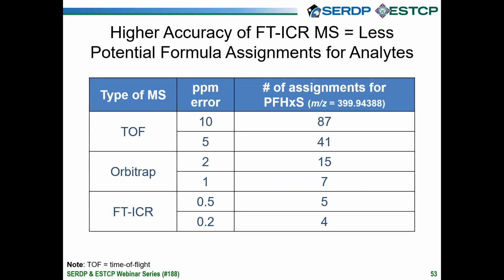So this ultra high resolution, when we look at molecular weights or masses, is a very strong line of evidence. We heard about time of flight mass spectrometers, or high resolution mass spectrometers, and the ppm error that is typically tolerated in the previous presentation. For a time of flight mass spectrometer, we're typically hoping to be somewhere around 5 ppm error, sometimes we get to 10.